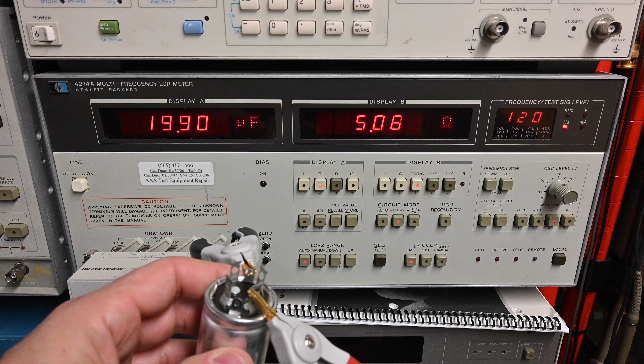I've got the LCR meter set to 120 Hertz. It's reading 29 microfarads and 3 ohms of ESR. The next section is the square, which is 20 microfarads. It's testing 19.92 at 4.47 ESR. And triangle, 19.9 microfarads at 5 ohms of ESR. And the circle, 20.3 microfarads at 4.62 ohms of ESR.